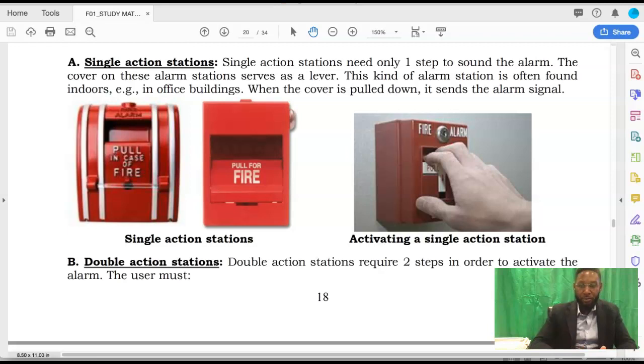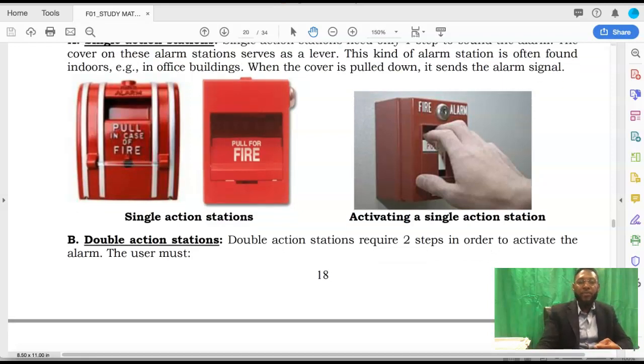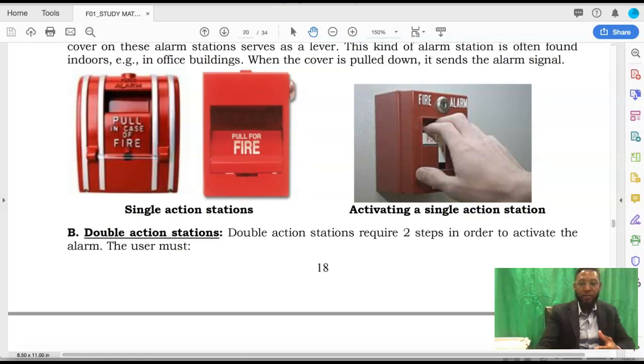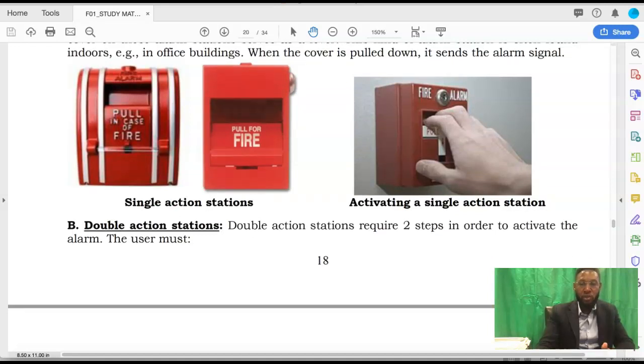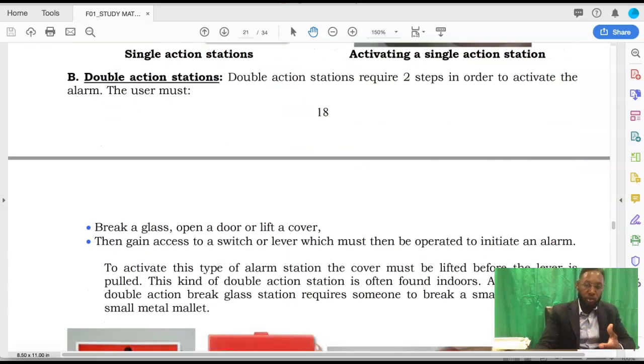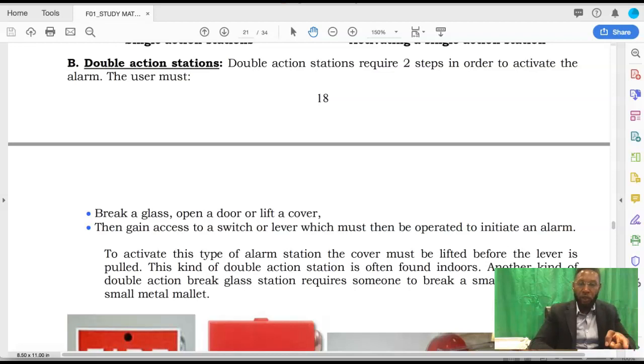Versus a double. The double action stations require two steps in order for the alarm to be activated. The user must apply two steps, which are: break a glass, open a door, or lift the cover, which is one step, depending on the kind of double action station you have operating in your building. Then gain access. Gain access to switch or lever, which must then be operated to initiate an alarm.